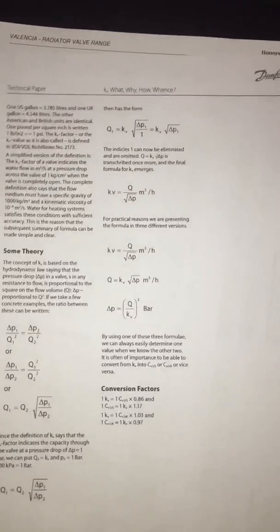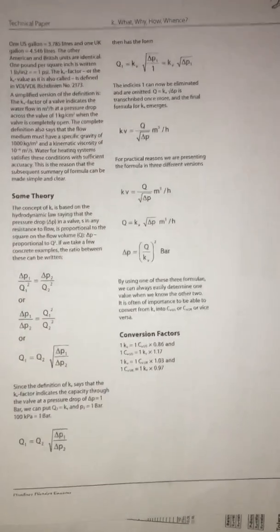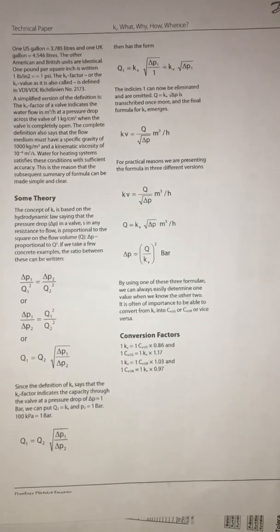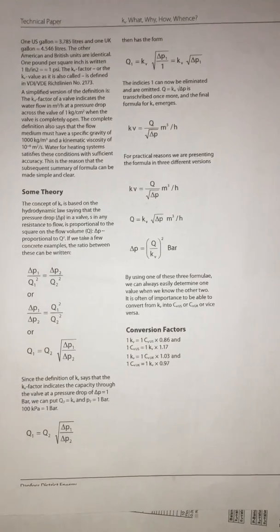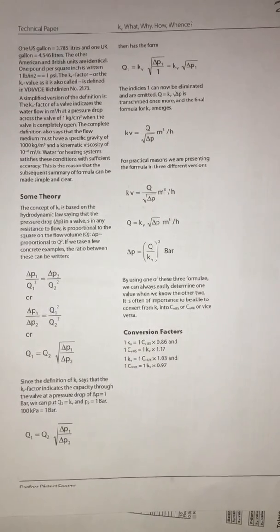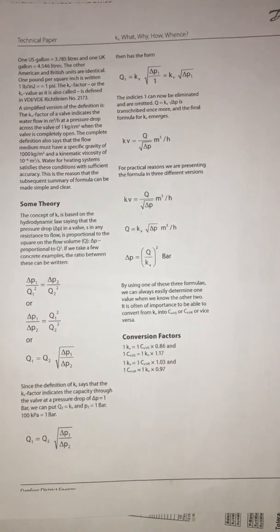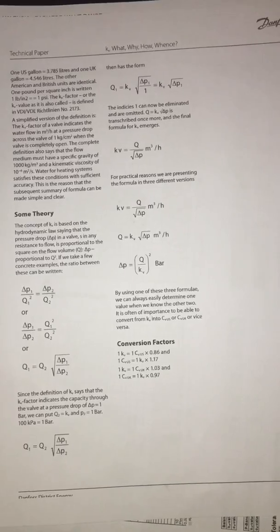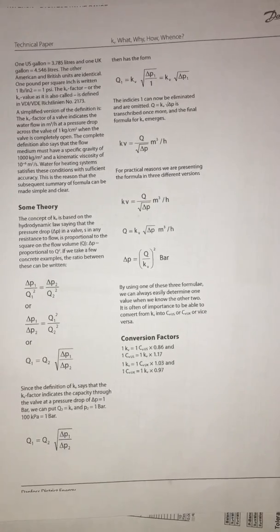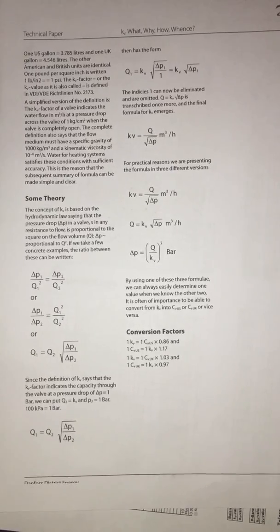But first just a little bit about flow coefficient. Flow coefficient will tell us how much flow in cubic meters per hour the valve will take to lose one bar of pressure. This is useful because there is a square law relationship between flow rate and pressure loss. So if we double the flow rate from a valve we will quadruple the pressure loss, or if we halve the flow rate the pressure loss will reduce to a quarter of its previous value.